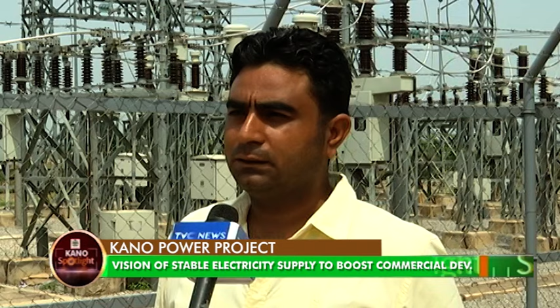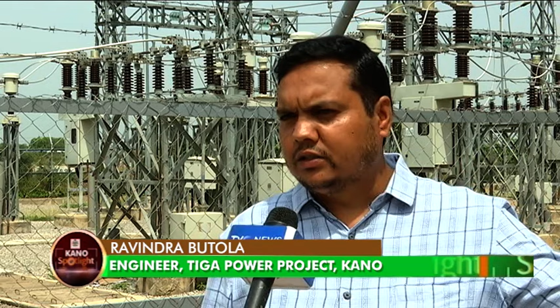This power will give resources to set up industries, and from the industries, people get employment, so everybody will benefit. There are two turbines, one vertical coupler and one horizontal coupler. Everything is ready, water is at the doorstep of the turbine, so we are ready for generation. At the back, you can see two transformers, each 7.5 MVA capacity, and the 33 kV switchyard installed and already commissioned, complete.